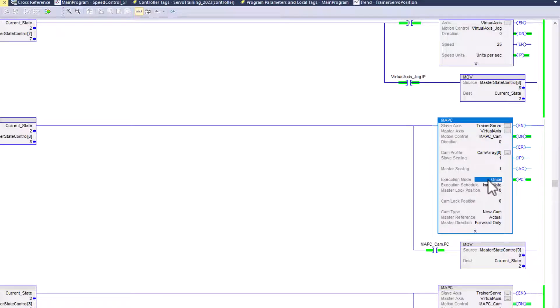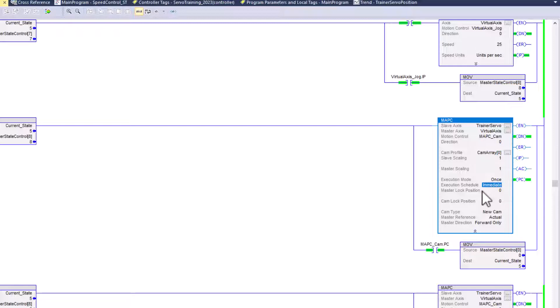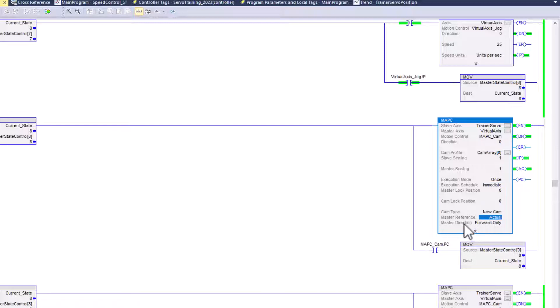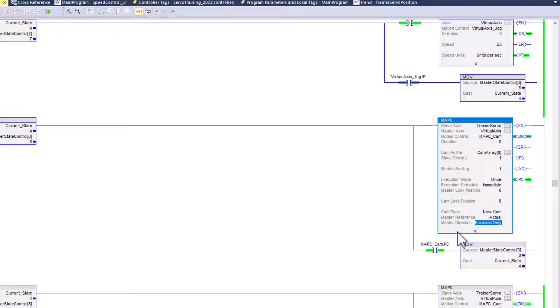So in the way I have it set to initiate is an execution mode of once, and then I want to immediately execute as soon as I tell the actual instruction to fire. So in this case, this is a new cam actual master reference. I'm using actual forward only, so only in the forward direction. So those are a couple of things.